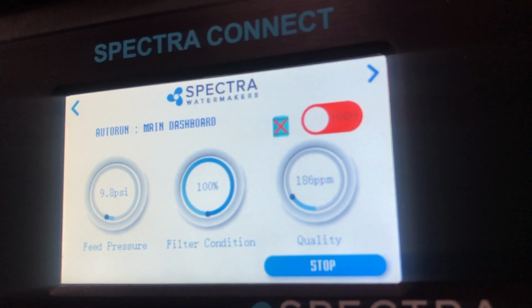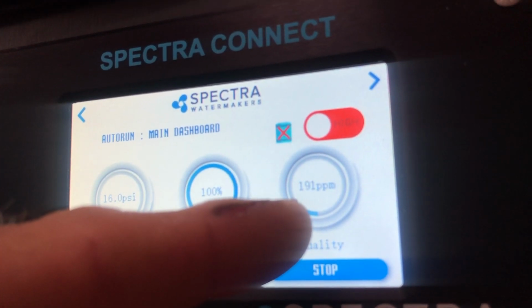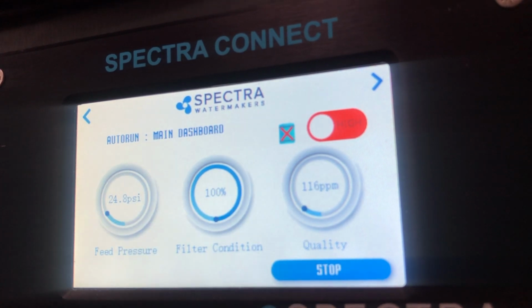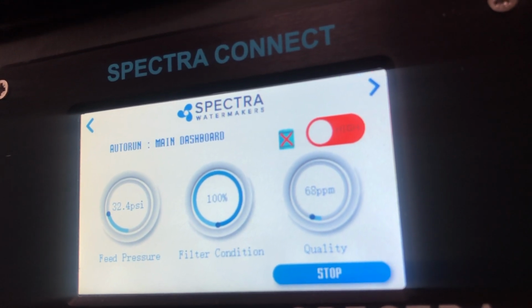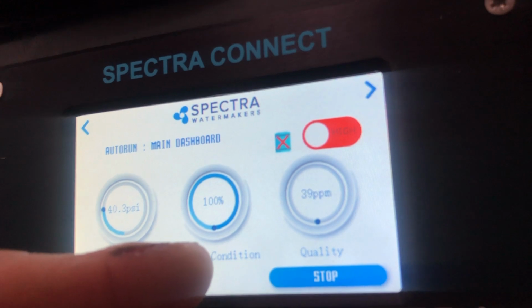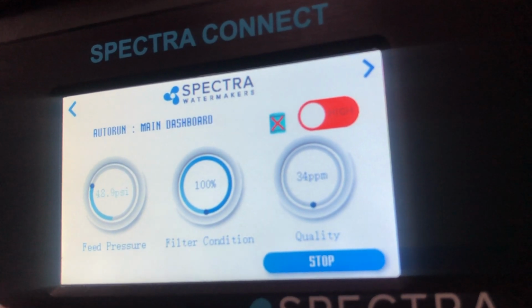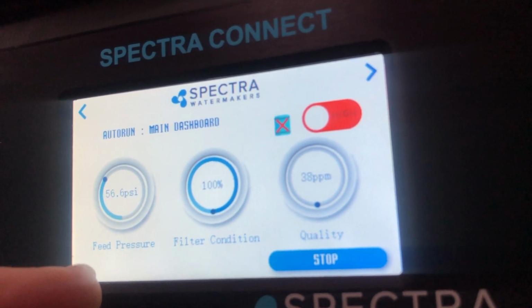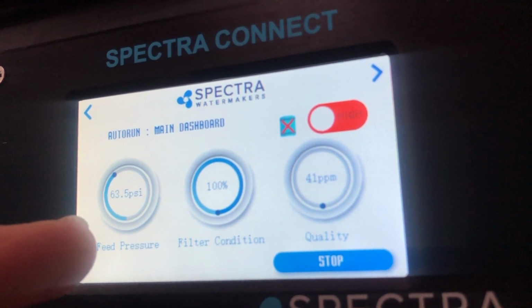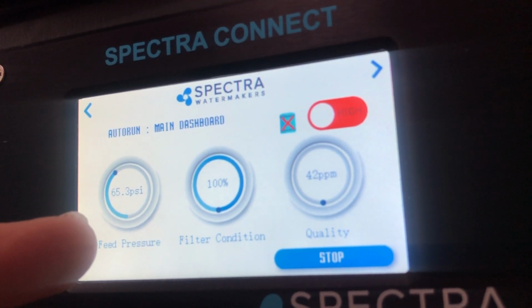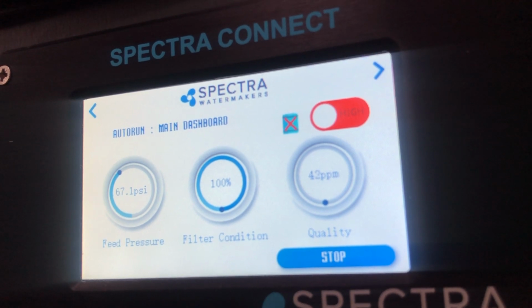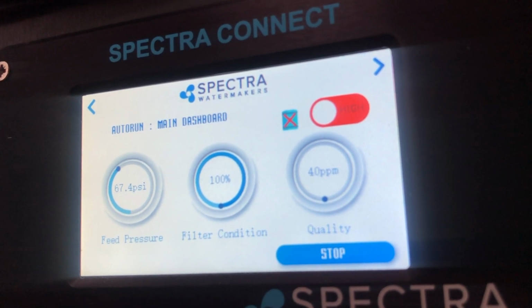Boom, there's your 3 windows. This is the number we're looking for. This is our parts per million. It'll be high right now until the pressure starts building up, and it'll start dropping. Here's your filter condition at 100%. Yeah. Good. And this is your feed pressure. That's that white box, the feed pump module. I said you'll see things between normally offshore 90 to 120 psi. Right now it's low because the water is very fresh.